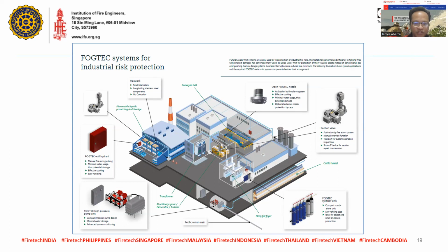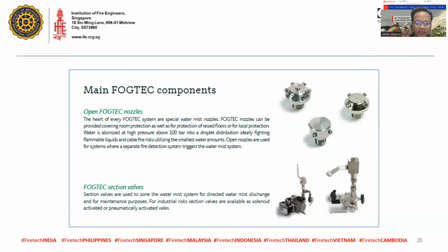If you have a project application wherein you don't need a centralized high pressure pump, there is also a cylinder type of water mist, which is a combination of water and nitrogen. As you can see on the bottom corner, the blue and the white. This can be applicable to replace FM200, Novec 1230, CO2, or any clean gas suppression system. Water mist is one of the best options.